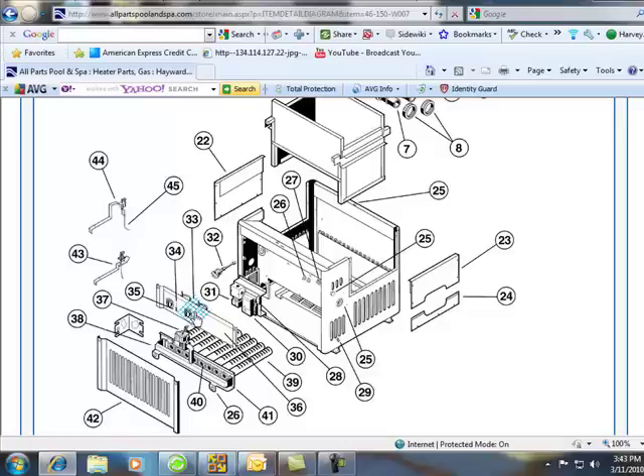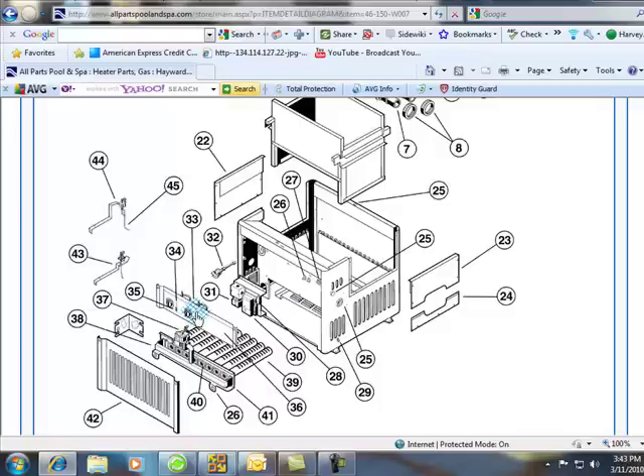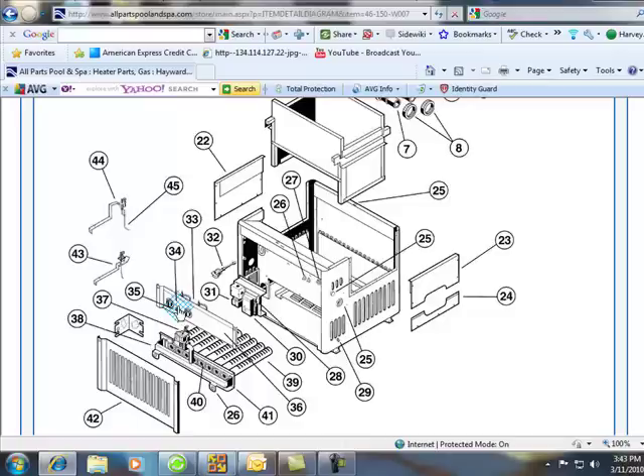Then we don't just want to check the unit itself. We want to check the wiring. So we want to ohm out the wiring and make sure these stab tabs are clean. I saw plenty of times where they're dirty and it just needed a new stab tab. Then we go to the switch if that's the next thing. And we ohm out the switch.